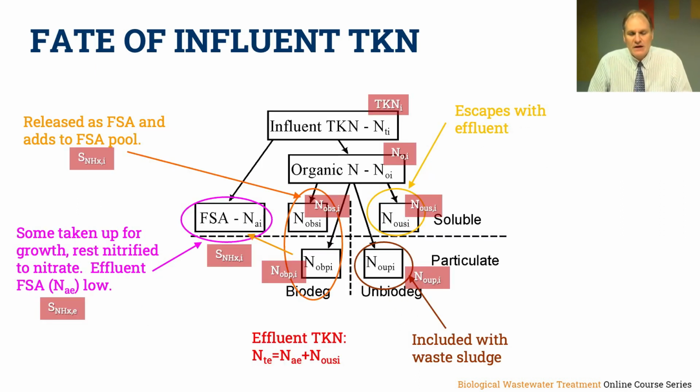Let me explain the influent wastewater characteristics now defined from the nitrogen standpoint. And we have our influent total Kjeldahl nitrogen. And we have our influent free and saline ammonia. I presume you already understand how we measure the influent TKN concentration and how we measure the influent free and saline ammonia concentration. But just to recap briefly, the free and saline ammonia concentration is measured by raising the pH of the sample to about 10.